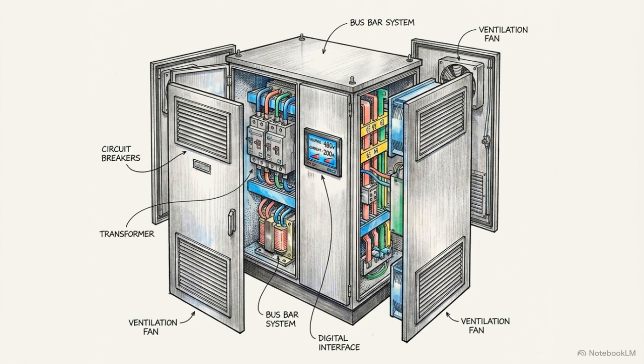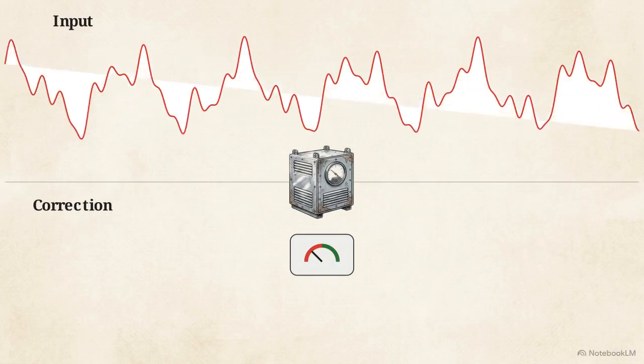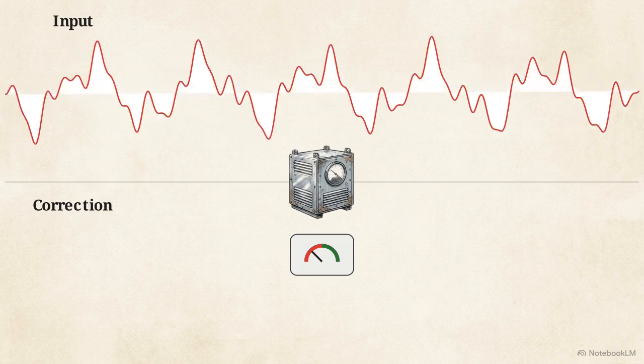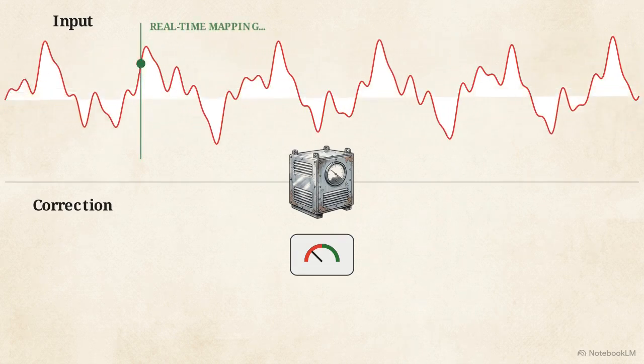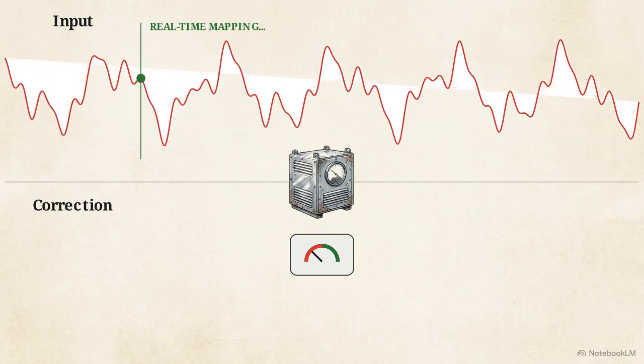The engineering solution to prevent grid meltdowns is a device known as an active harmonic filter. Think of this filter like industrial noise-canceling headphones. It monitors incoming dirty power waves from chargers in real time, mapping every single distortion.